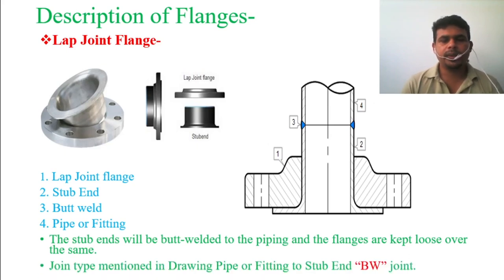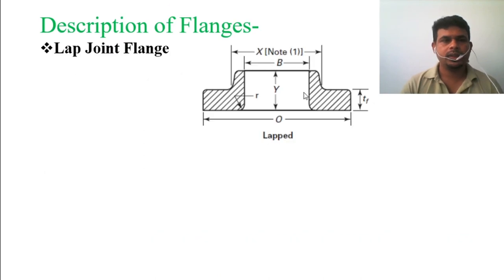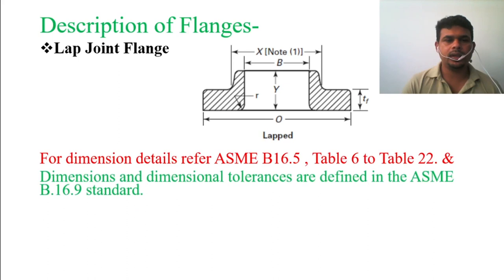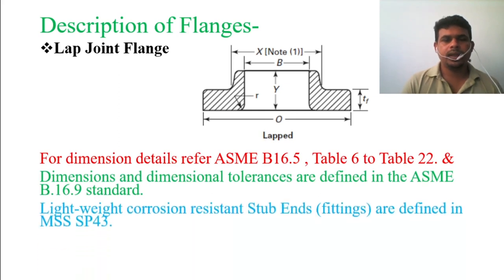The joint type mentioned in the drawing for pipe or fittings to Stub End is a butt joint. Looking at the flange dimensions, the chamfer and radius make the surfaces smooth. For more details, refer to ASME B16.5 Table 6 to Table 22, and ASME B16.9 for dimensional tolerances. Lightweight corrosion-resistant Stub End fittings are defined in MSS SP-43.